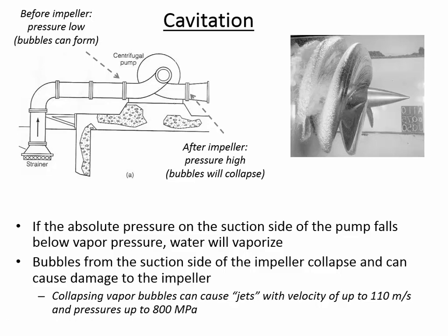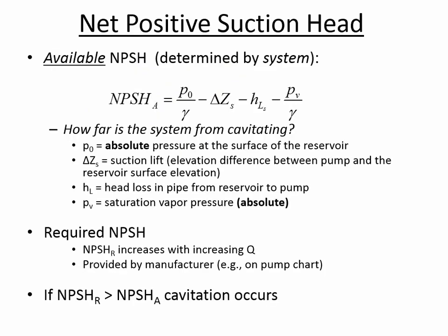And you may notice that actually when you buy a pump from a manufacturer, oftentimes the suction side hose is a larger diameter than the discharge side hose. And that was the case when I was in graduate school. I had to buy a couple of pumps for an experiment that I was doing, and in each case they give you a really big fat suction side hose because the lower the velocity, you're going to have less losses due to pipe friction. And then the discharge hose was a smaller diameter because there's no risk of cavitation on the pressure side. It's just on the suction side that the cavitation occurs.